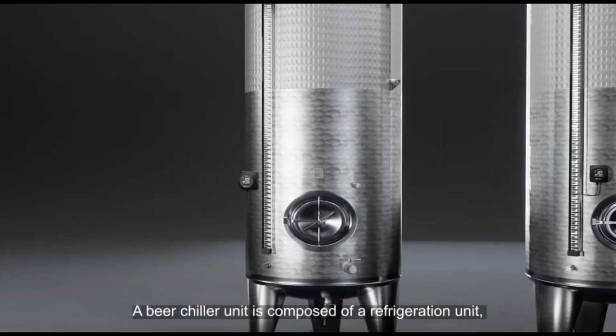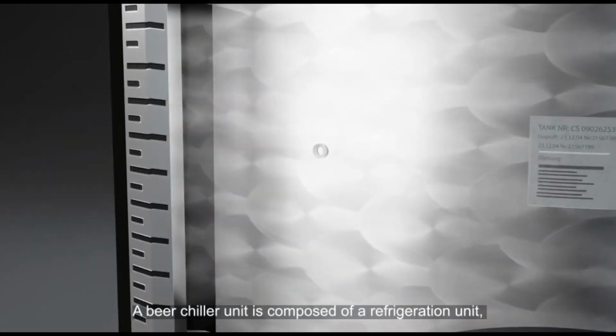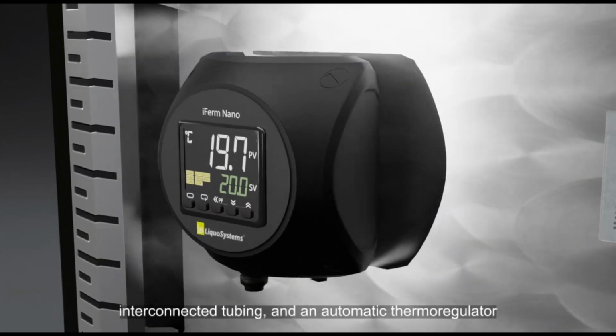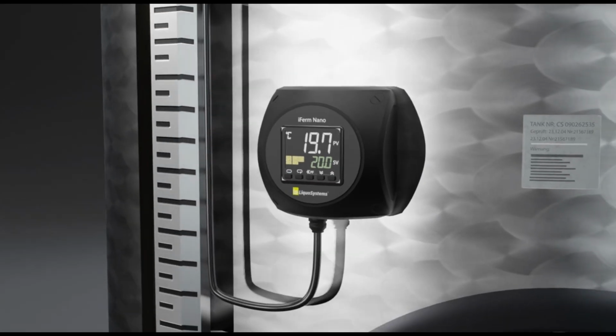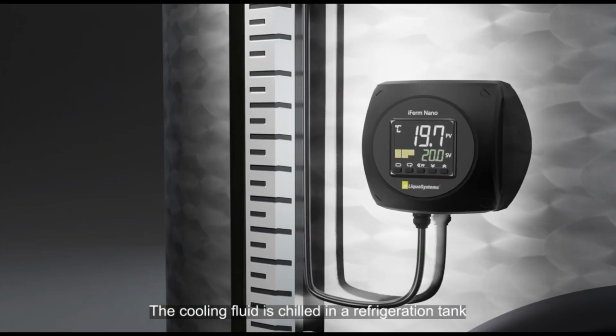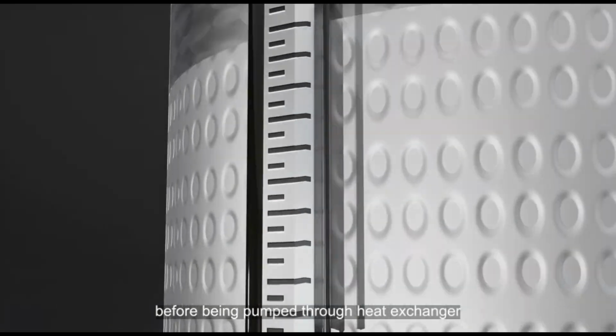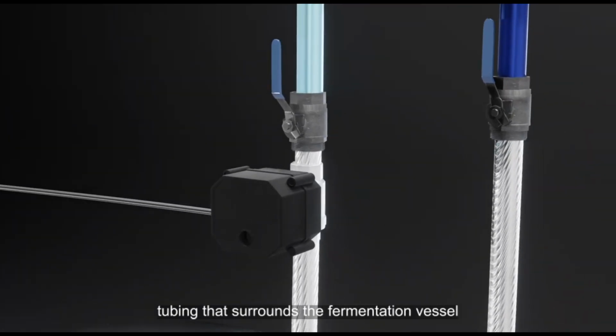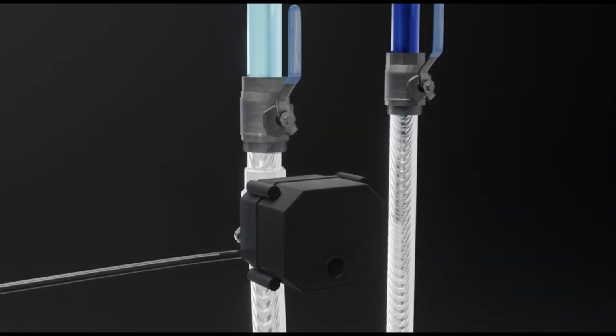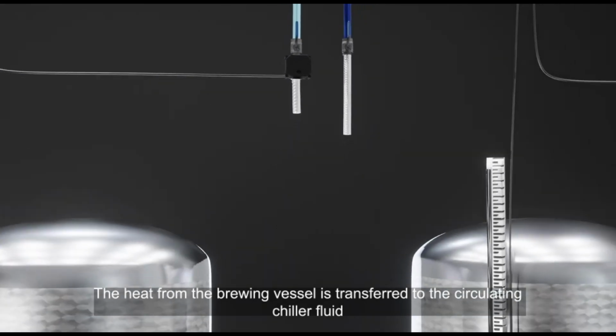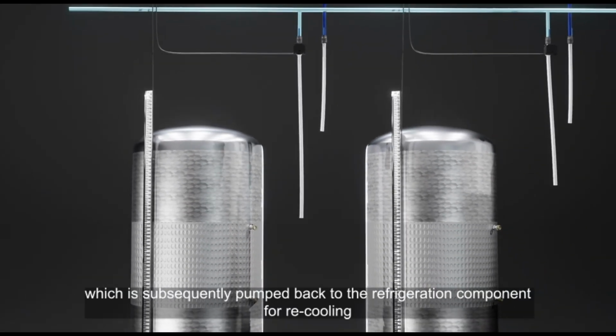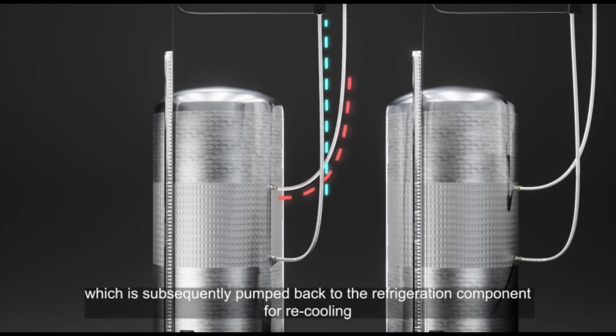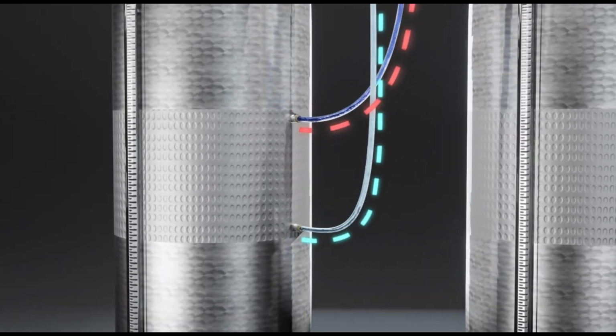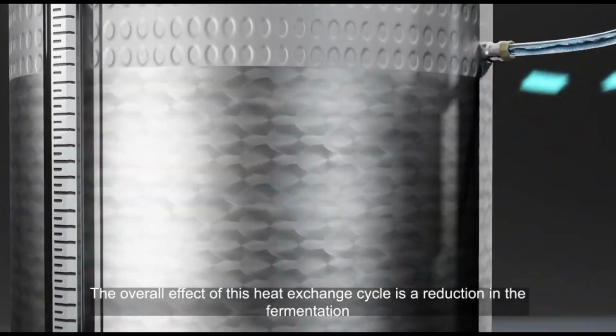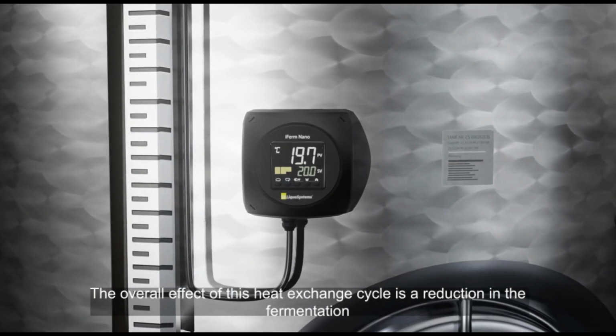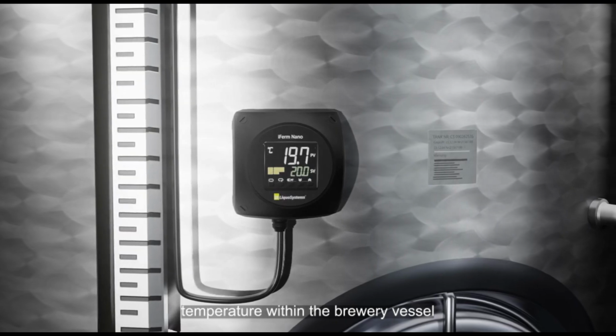A beer chiller unit is composed of a refrigeration unit, interconnected tubing, and an automatic thermoregulator. The cooling fluid is chilled in a refrigeration tank before being pumped through heat exchanger tubing that surrounds the fermentation vessel. The heat from the brewing vessel is transferred to the circulating chiller fluid, which is subsequently pumped back to the refrigeration component for recooling. The overall effect of this heat exchange cycle is a reduction in the fermentation temperature within the brewery vessel.